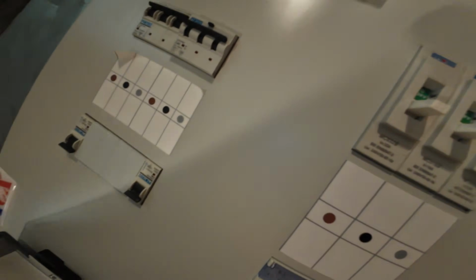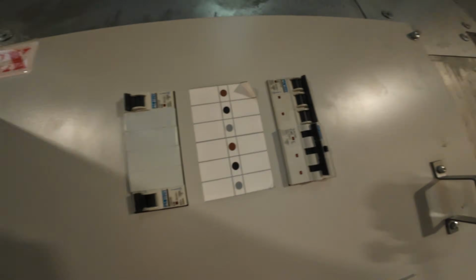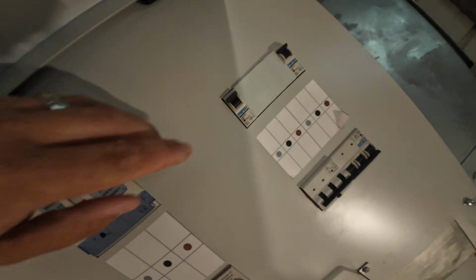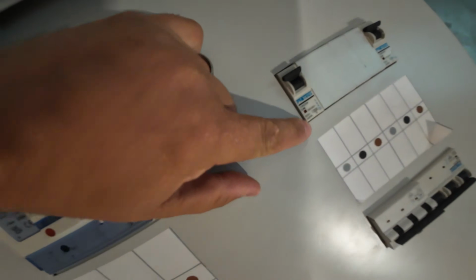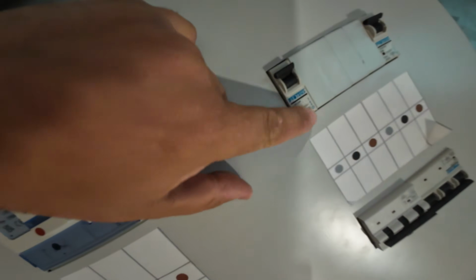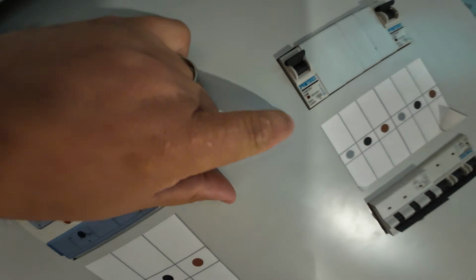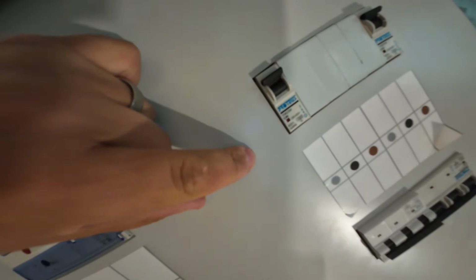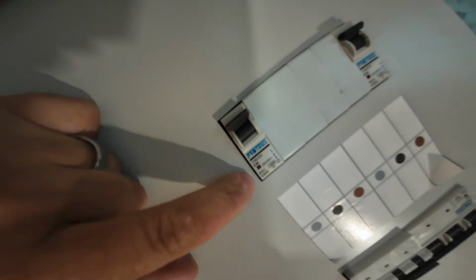Now it is possible with some manufacturers, and I think Proteus is one of them, where you can get dual product standard devices. You would have something that looks like this, and it would be 60898 and 60947-2 rated, and its kA rating adjusts accordingly depending on which application of that product device you are using.